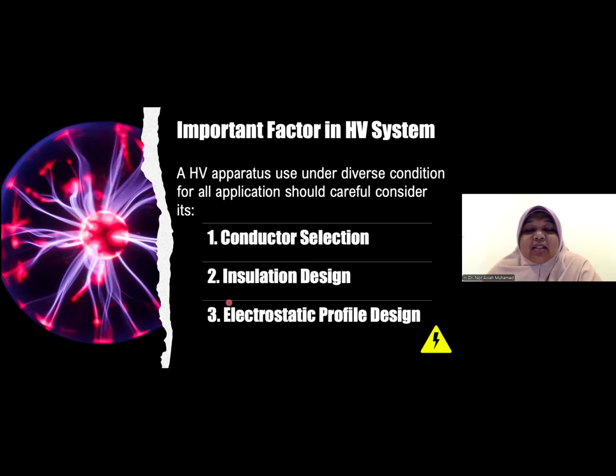So insulation design matters, because it carries high current or produces high voltage. The important thing is the insulation design, because to carry the current we need only solid material, but to make the operation safe, we must design a good insulation system. So in high voltage, the most important are the insulation design and the electrostatic profile design.